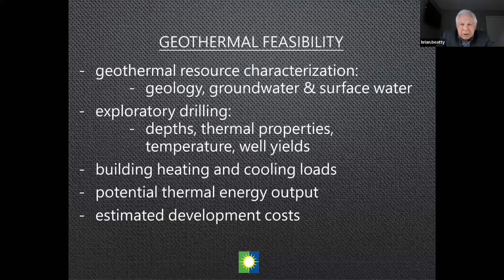Next you look at the energy loads for the building, since every geothermal system is connected to a building or multiple buildings. To size the system you need to know the heating and cooling loads. Then you determine the thermal energy output of the field to see if it matches those loads, and you determine development cost, since everyone needs a rough idea of what it's all going to cost. That's the last step in a feasibility study.